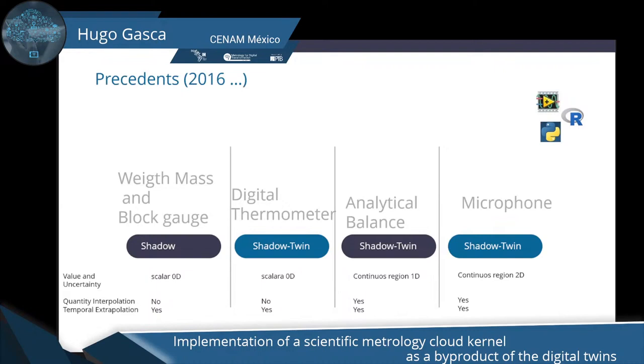The third example is an analytical balance. It's a continuous response to the stimulus. If you have a 2 milligram mass compared to 20 milligrams, 200 milligrams, any intermediate value will give us a response, both for the value and also for uncertainty. And here we start to look at the possibility of controlling the response of the instrument, of the device. It could be a shadow, a digital shadow, and a digital twin. And here we need interpolation between the values.